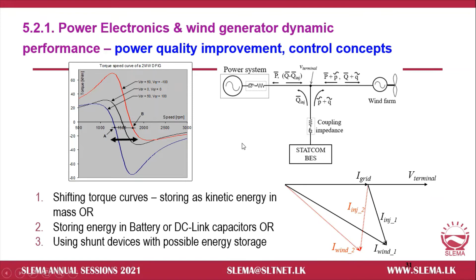Especially with STATCOM with battery energy storage, you can maintain the grid voltage and grid current in phase and constant. Whatever fluctuating current is taken by the wind turbine, by injecting the fluctuating component from the STATCOM, you can keep the grid current constant and in phase with the grid voltage. So basically unity power factor and constant power can be pumped to the grid. The fluctuating component is transferred between the STATCOM (with battery energy storage) and the wind turbine. This is how these control concepts work to improve power quality using power electronic devices in the latest wind turbine technologies.